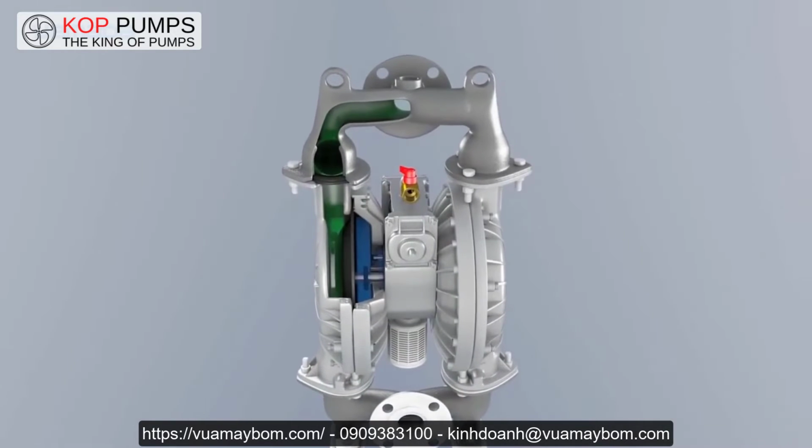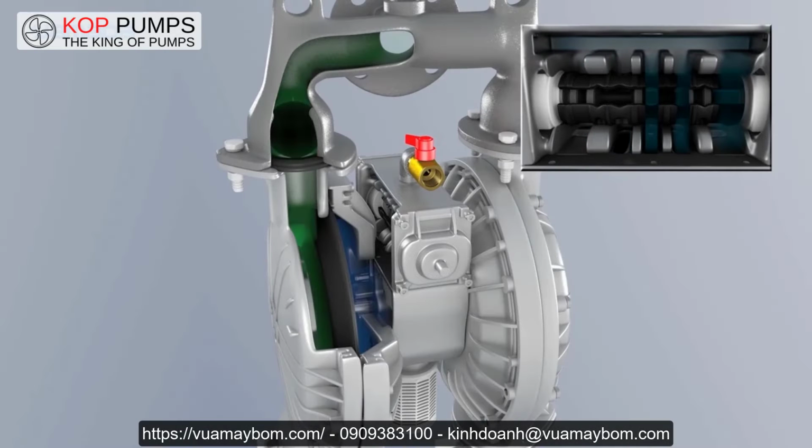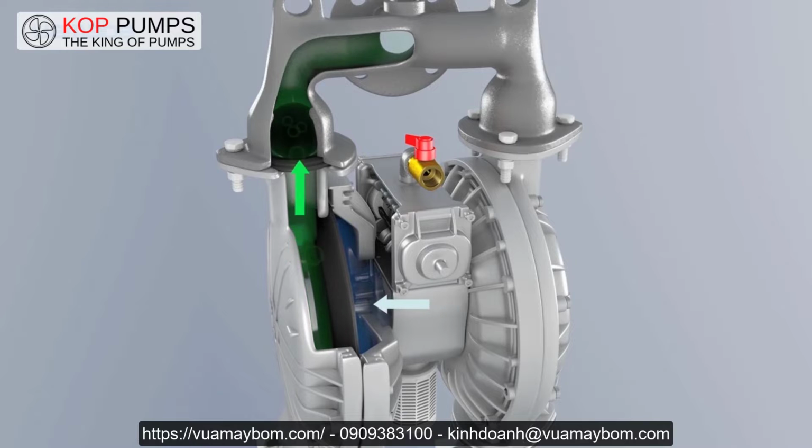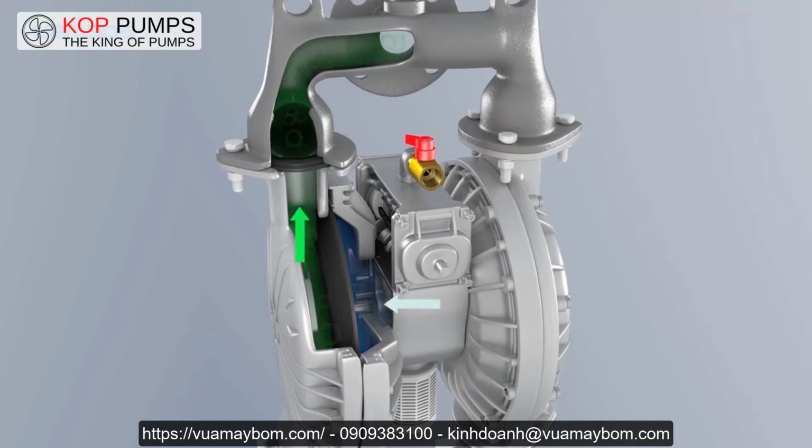As compressed air enters the pump, it is directed via the main air valve to one side or the other, depending upon the starting position of the C-spool. As the air enters the chamber, it forces the diaphragm outward. This outward momentum forces liquid out of the discharge ball valve and loads the opposite inlet ball valve. As the diaphragm travels outward, the connected diaphragm on the opposite side is pulling the diaphragm inward.